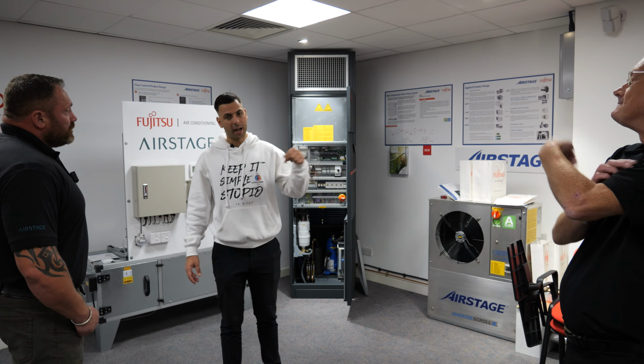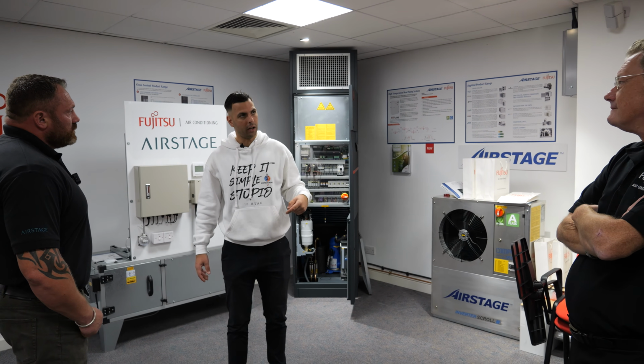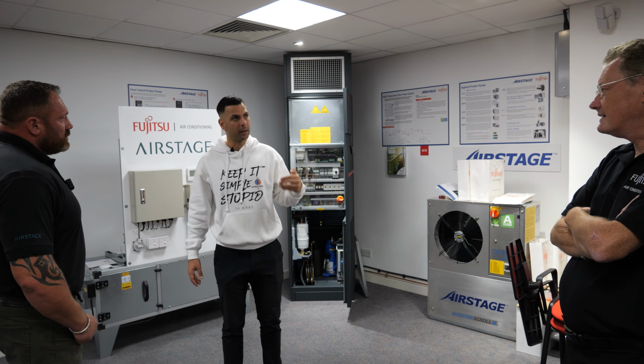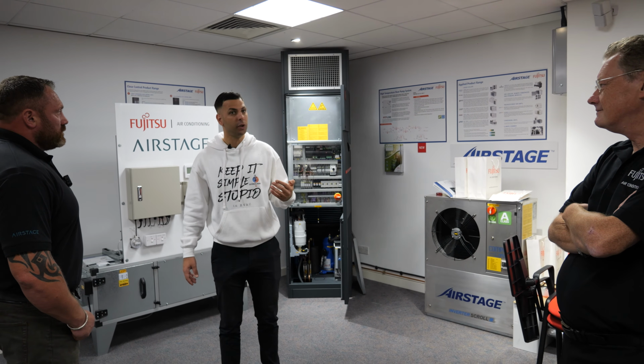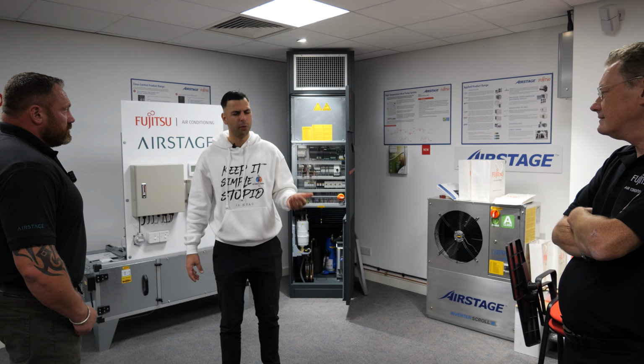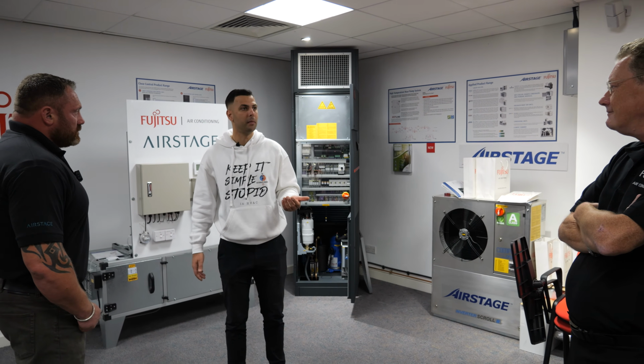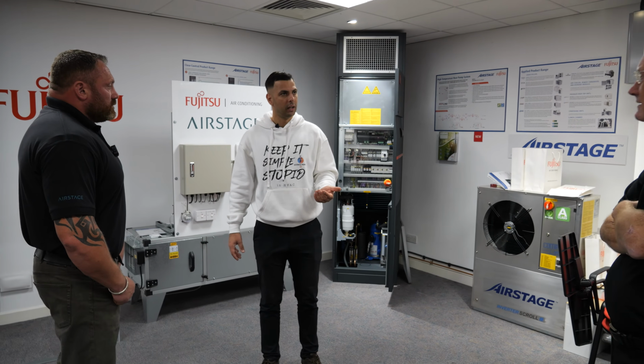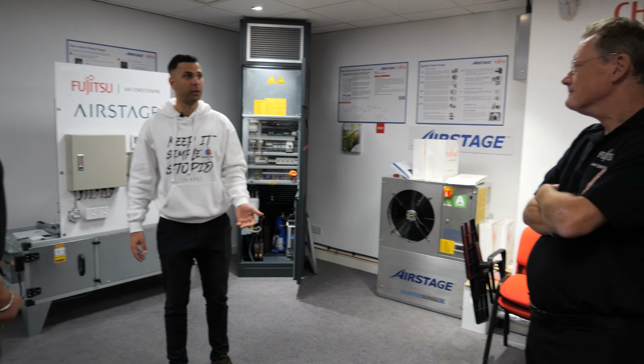However, if that wasn't a Fujitsu solution at Leicester Court, you'd have great big three-phase preheaters because no unit works below 16. I think it's 14 or 16. It has to have a minimum of 14 to 16 degrees. You need preheat, which is super expensive to run.